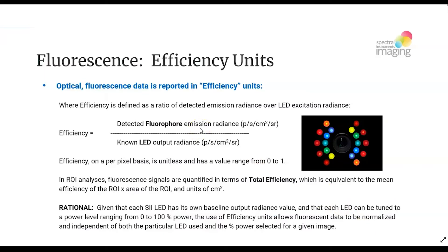You may ask: what exactly is efficiency? Efficiency is a ratio value where we're looking at the relative radiance of the fluorophore detected over the known radiance output of the LED that is being used to excite the fluorophore in the first place. Efficiency values generally range from zero to one, where zero would be no detected fluorophore signal, and one would be where the fluorophore signal is essentially equal to the LED output — which quite honestly never happens.